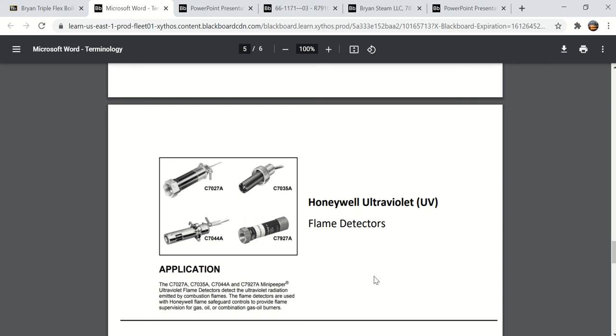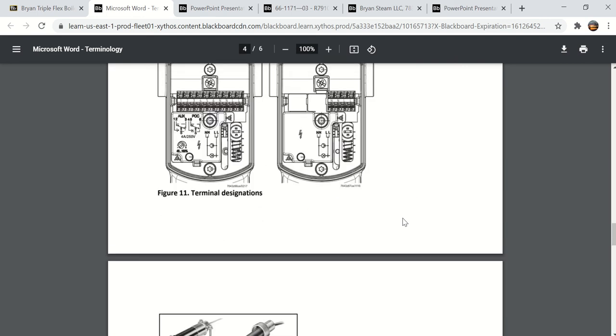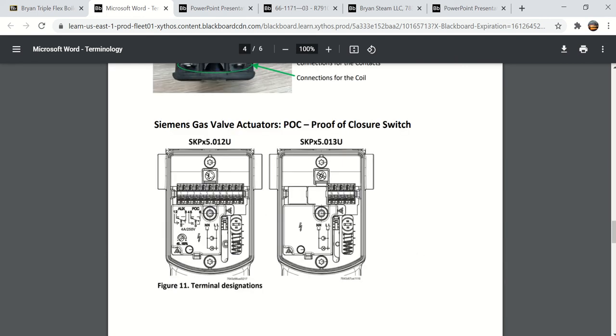And on almost all boilers or burners, you can actually measure the flame signal that this is actually seeing, and you can on this, and we'll get to that when we look at features of the touchscreen display. You can actually see the flame response, flame signal, and the strength. One thing I skipped over here, I want to get back to this proof of closure thing that we talked about in the first video.